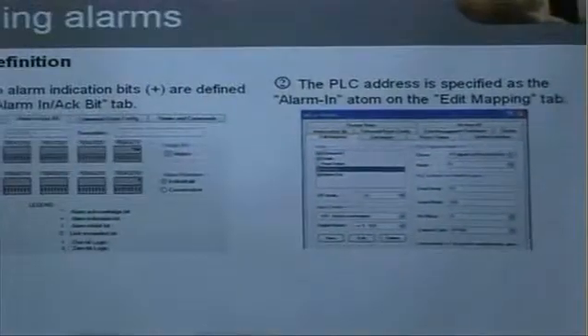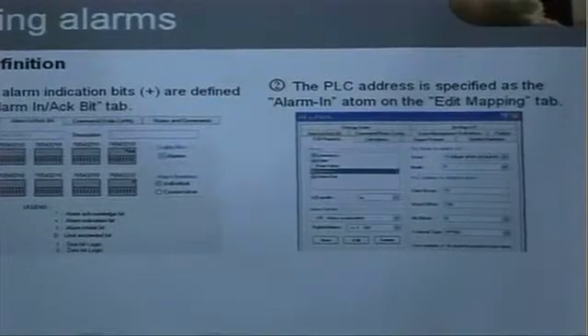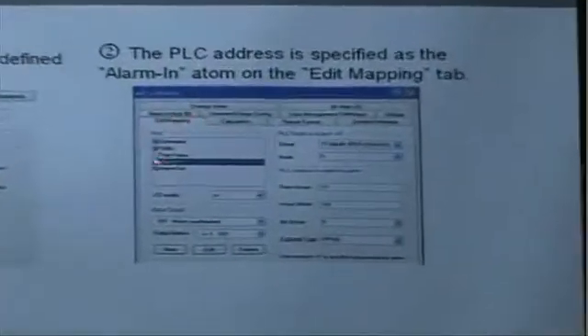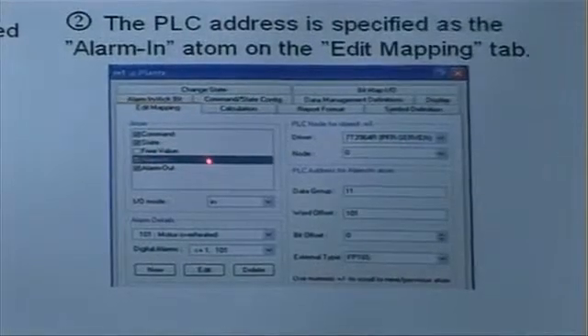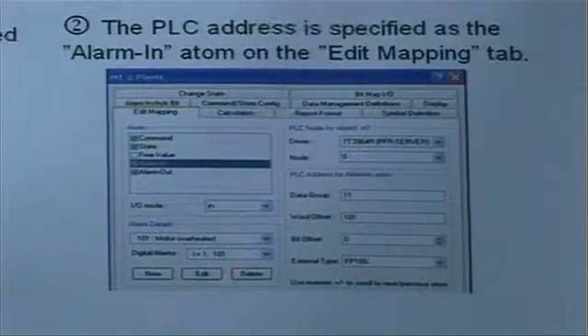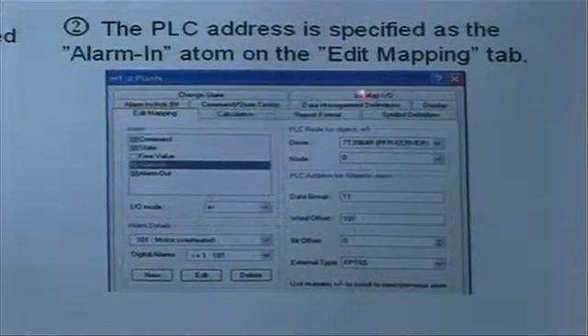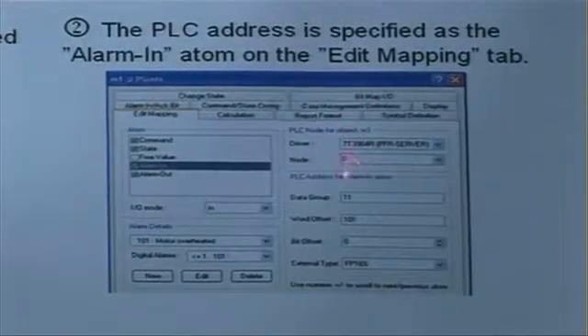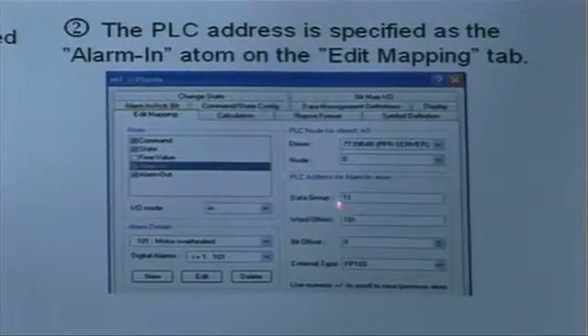The next step is to define the PLC address for those two alarm bits that we have just specified. We go to the edit mapping tab where we specify the PLC addresses. We select the alarm in atom, the in/out mode is of course 'in', and we specify the PLC address. We have our driver, our node number, and we specify the PLC address here.